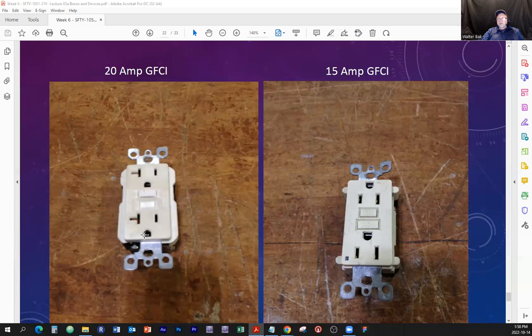What else do we have to replace? We have to make sure that the cable that connects the circuit breaker to the device is also capable of carrying the 20 amps. American wire gauge. Yes, there we go. So what is rated for 20 amps? Well, gauge 12 is rated for 20 amps. So we have to replace the cable as well.